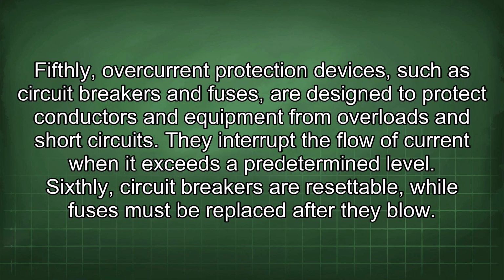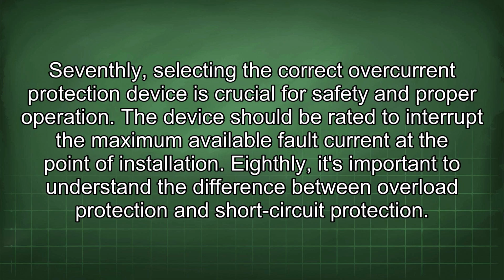Fifthly, overcurrent protection devices such as circuit breakers and fuses are designed to protect conductors and equipment from overloads and short circuits. They interrupt the flow of current when it exceeds a predetermined level. Sixthly, circuit breakers are resettable, while fuses must be replaced after they blow. Seventhly, selecting the correct overcurrent protection device is crucial for safety and proper operation. The device should be rated to interrupt the maximum available fault current at the point of installation.